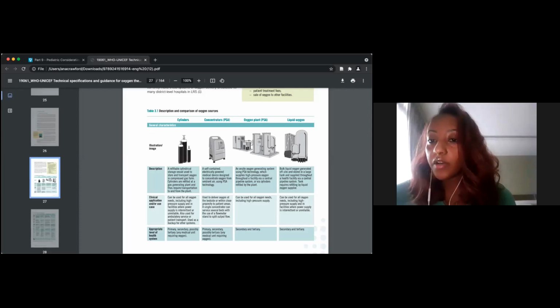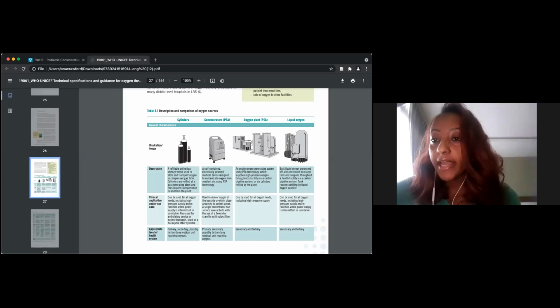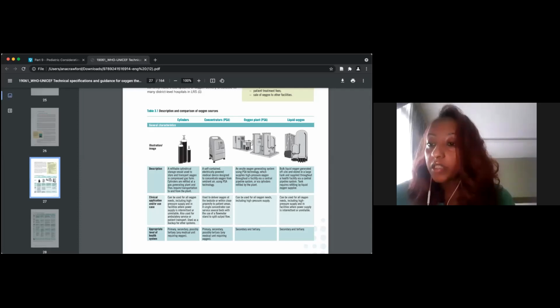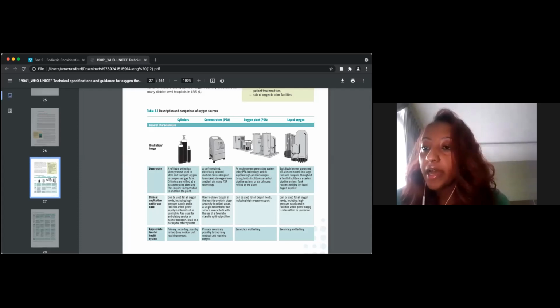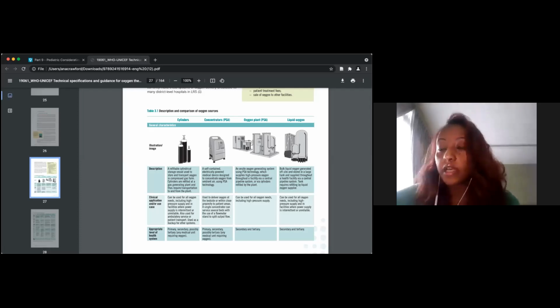When it comes to oxygen concentrators, they are well-contained, electrically powered medical devices designed to concentrate oxygen from ambient air using PSA technology. And oxygen plants are oxygen generating systems using PSA technology, which supply high pressure oxygen throughout a facility via a central pipeline system, or via cylinders refilled by the plant. Liquid oxygen is bulk liquid oxygen generated off-site and stored in a large tank and supplied through a health facility via a central pipeline system. It requires refilling by a liquid oxygen supplier. So that is their description.